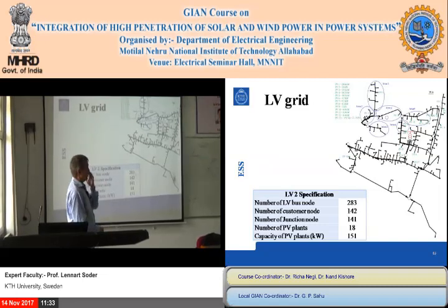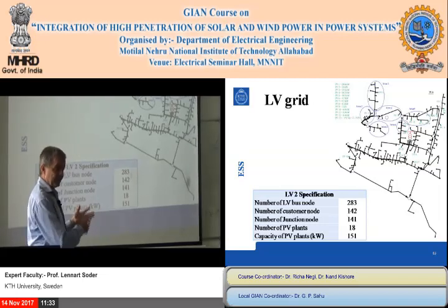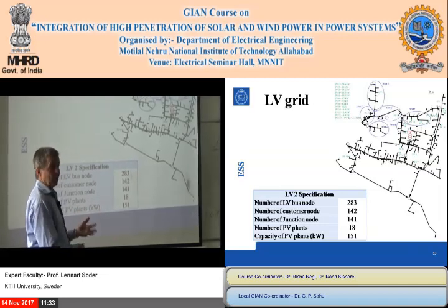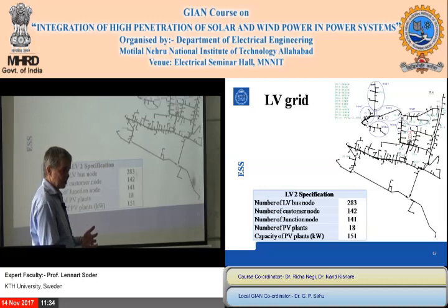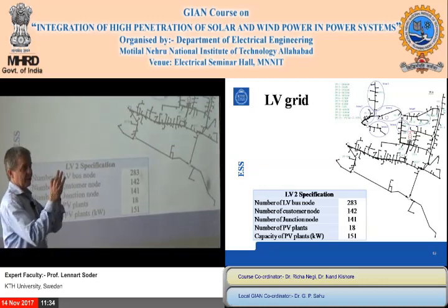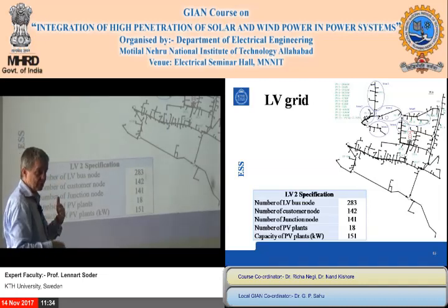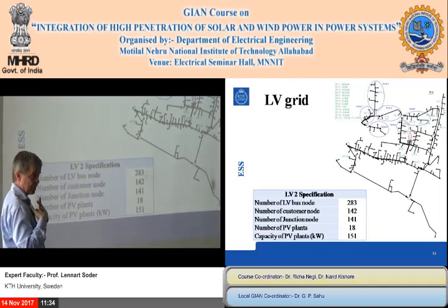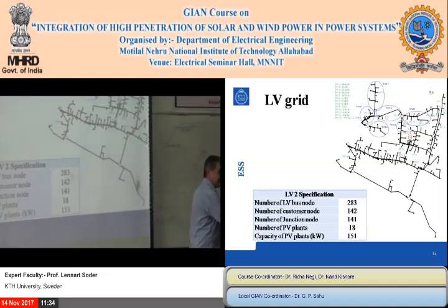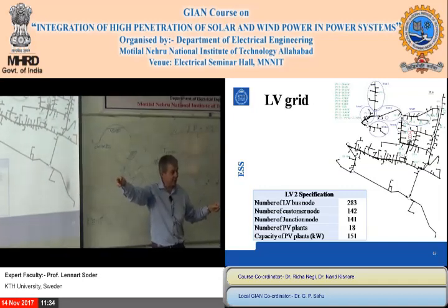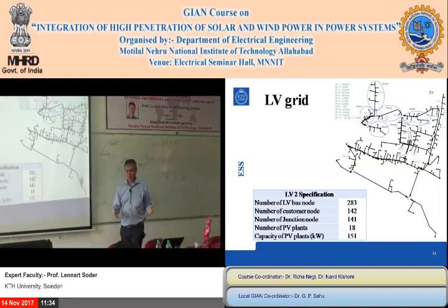For example, this is the case with the RX quota. It is different in different grids, but what is the normal R and X in a grid? That was one of our first things that we identified. In a true system, say a 20 kV system, normally in the beginning you have rather thick areas, because the grid owner is planning for a big current close to the transfeeding transformer. But further out you have thinner and thinner areas with the same X, which means that in the 20 kV grid you will get different XR quotas the further out you come. And then the question is, how is it in reality?